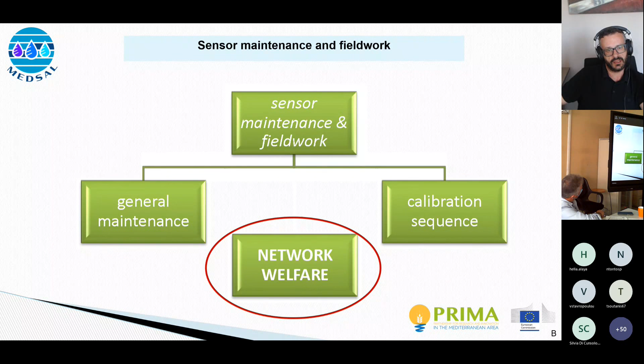Field operations may be distinguished into two distinct categories: the calibration sequence and the general maintenance, which leads to network welfare. So these are some do's and don'ts related to the calibration sequence. You have to use fresh standards. You have to study the instrument's manual very well. You have to exercise yourself on the instrument. You will not have time in the field to do it, so do it at your lab and be ready to use it in the field.